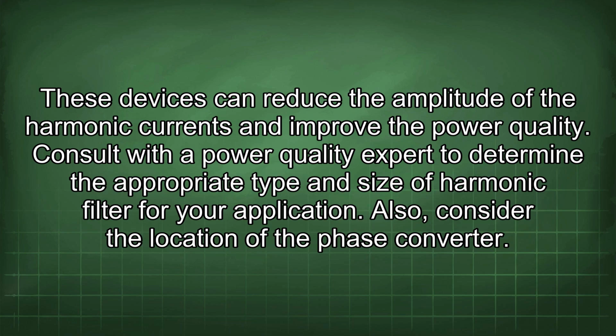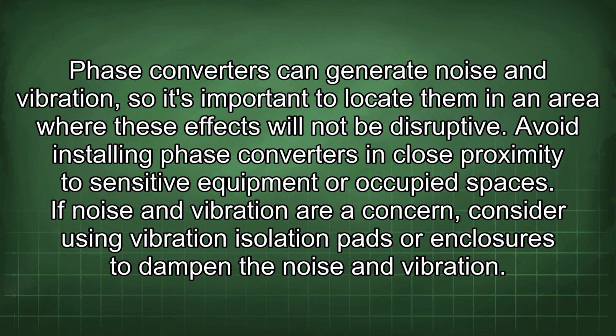Also, consider the location of the phase converter. Phase converters can generate noise and vibration, so it's important to locate them in an area where these effects will not be disruptive. Avoid installing phase converters in close proximity to sensitive equipment or occupied spaces. If noise and vibration are a concern, consider using vibration isolation pads or enclosures to dampen the noise and vibration.